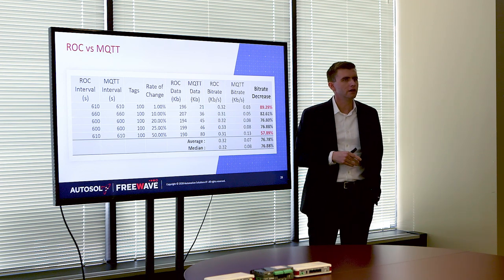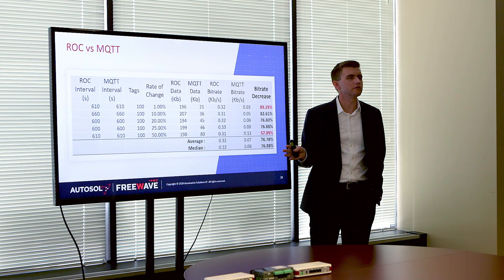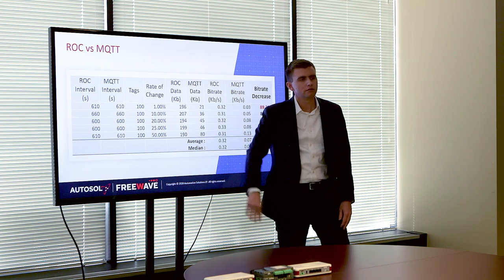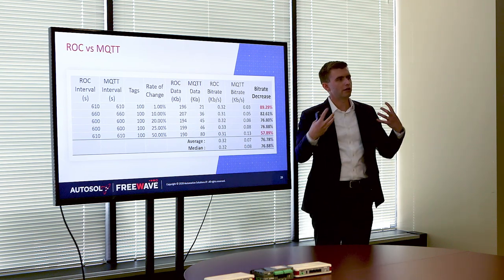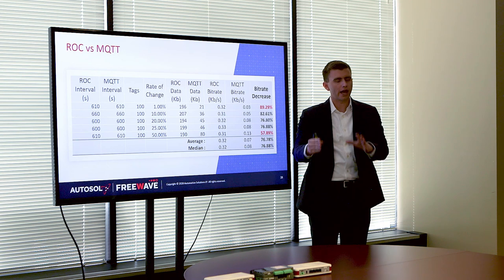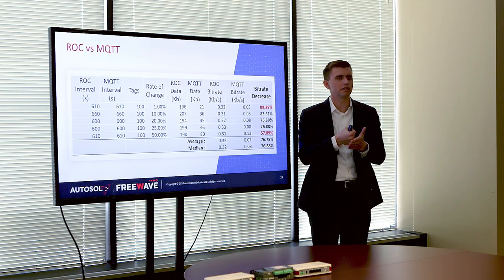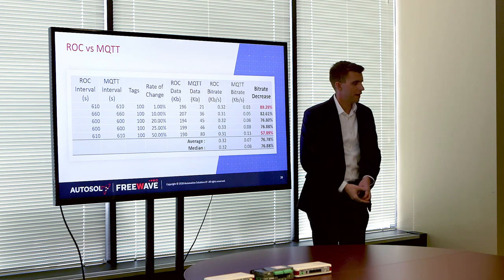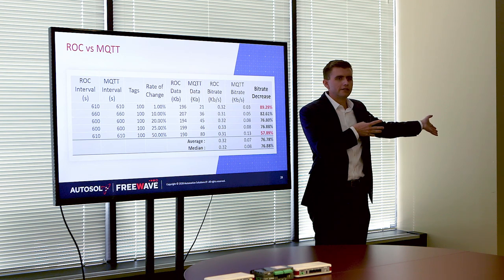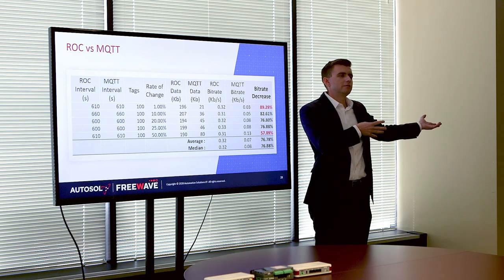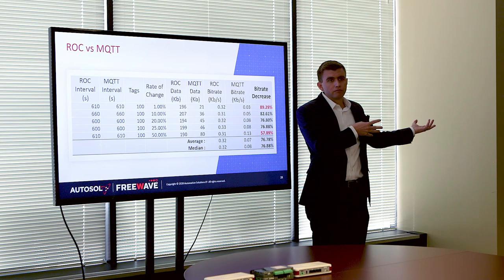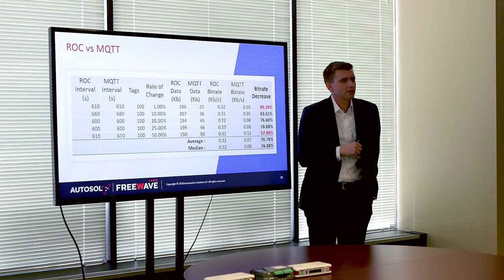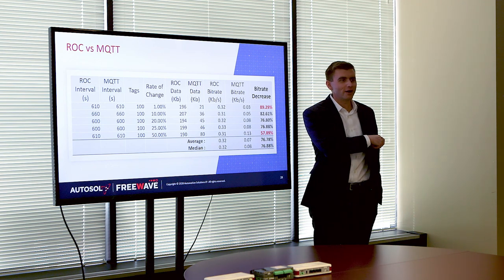Not as shocking as the Modbus, but still effective in the field. And doubly so when clients can separate tags into different tag groups in Edge ACM. For example, if you have a plunger well and you really care about five points, you can have them in a tag group polling every second or every minute, and all other 2,000 tags on a separate tag group polling once an hour. In that case, a client would see a 96.26% reduction of bandwidth consumption.